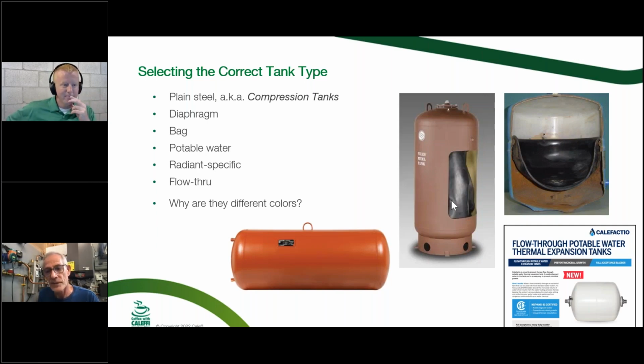And then on the lower right, that's kind of a unique tank too. That's a potable water expansion tank, and it's a flow through, because there is some concern out there. If you have a tank on a dead end leg, is Legionella on your domestic waters going to grow in there and then somehow get back into the system? I believe it's a stainless steel tank too, with a flow through design, which is clever. I've never used one, but I understand the intent there.